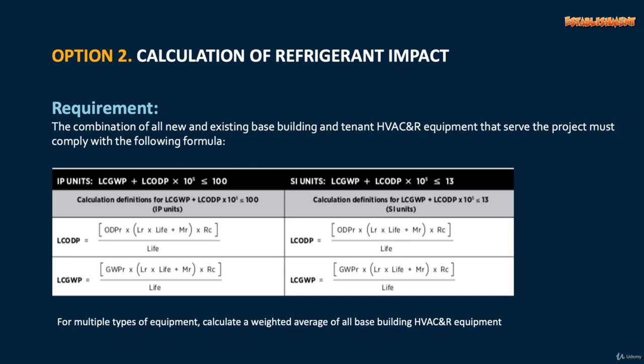So LCODP stands for Life Cycle Ozone Depletion Potential, and this is what we're calculating. Above the line we have the ODP or the GWP, which is the ozone depletion potential or the global warming potential. And we multiply this by the refrigerant leakage rate times the life of the equipment plus the end-of-life refrigerant loss. This is all between brackets, and then we multiply this by the refrigerant charge, or RC. And then all of this together gets divided by the equipment life. 10 years is the default, unless otherwise specified. So again, it looks somewhat complicated, but with a simple spreadsheet, it's easy to do. If you have multiple types of equipment, calculate the weighted average.